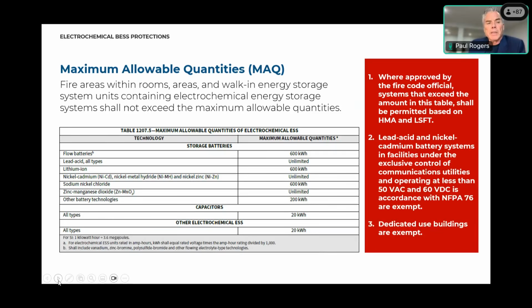How can they do that? By doing the large-scale fire testing and a hazard mitigation analysis. That gives you the right to go above, but you have to show in that data collection test that the system will not propagate or spread to the adjoining systems next to it. So even though these are the MAQs, there is a way out by doing large-scale fire testing inside the rooms, areas, walk-in containers, and even inside the cabinets themselves. These are just thresholds, and I wanted to make sure you understood those thresholds.